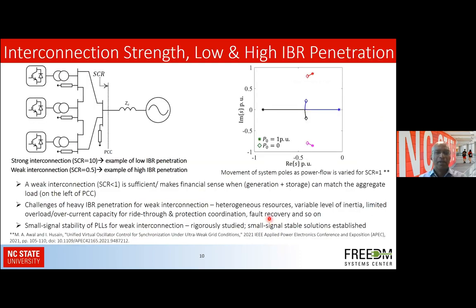One way of looking into or defining the high versus low penetration of IBRs, inverter-based resources, is through looking into the interconnection strength. So if we look at this system where we have a few inverter-based resources to the left of this point of common coupling that serve some local loads, and we have a generator system here connected to this grid impedance, which could be the transmission line. So we can argue that there is a weak interconnection where the short circuit ratio is low, seen from this point, which means that the grid impedance is high.